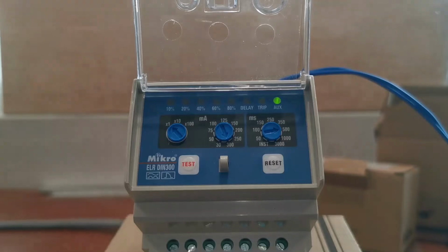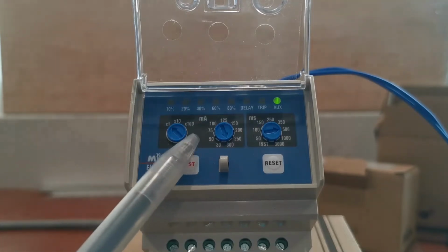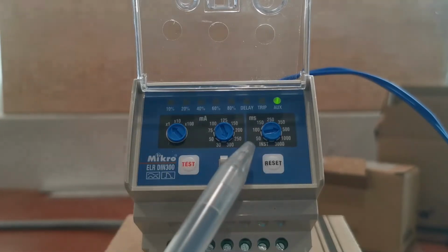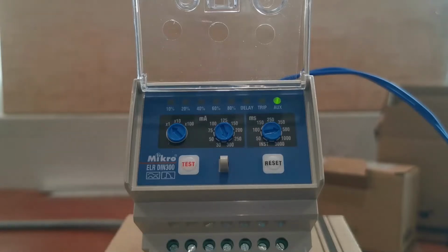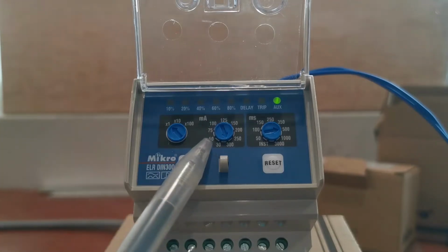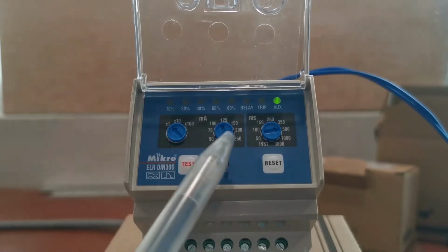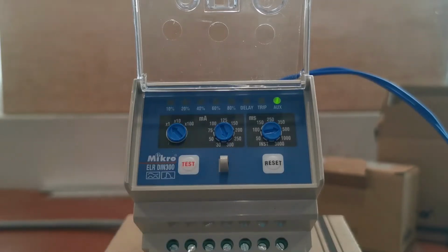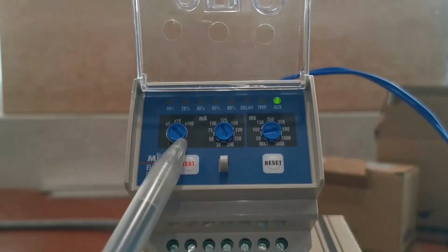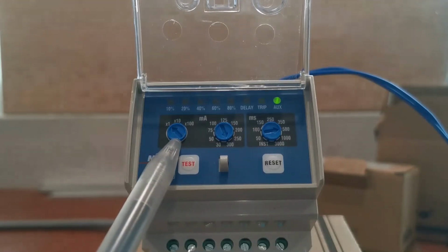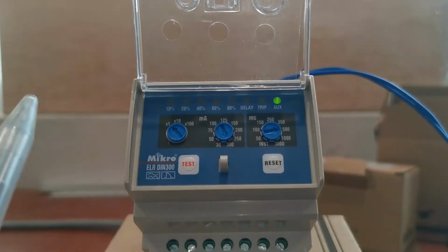The settings of this earth leakage relay have two groups. First is the sensitivity, which is here, and the second is the time delay, which is here. The sensitivity has two selections. The first one is the value in milliamps, so the range starts from 30 to 300 milliamps. The second dial here shows the multiplier of the sensitivity current setting.